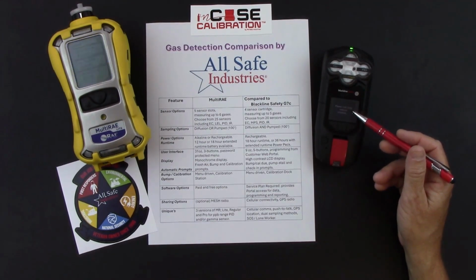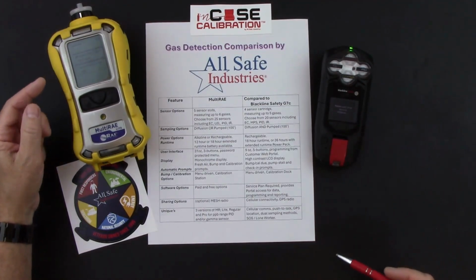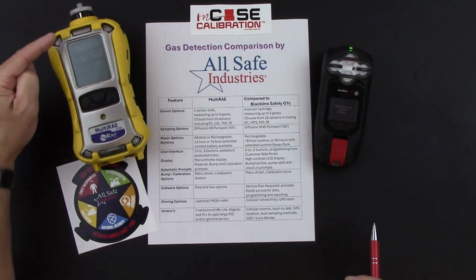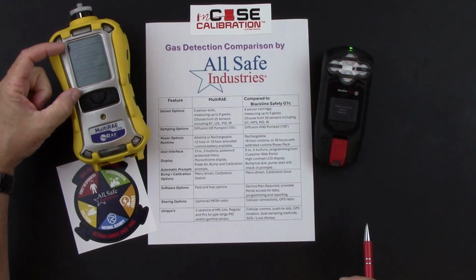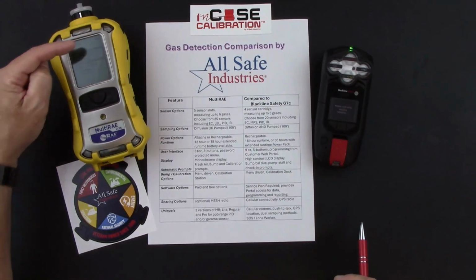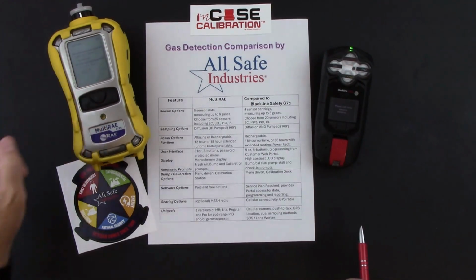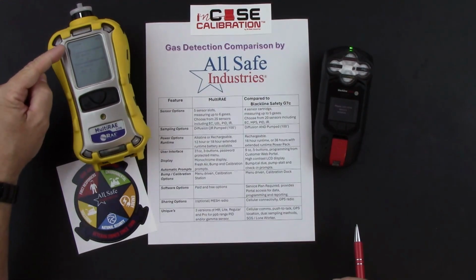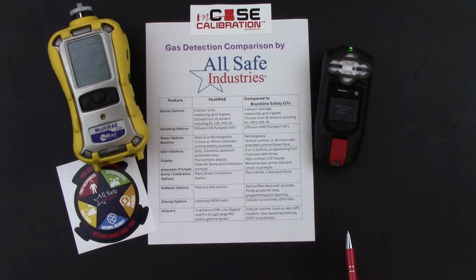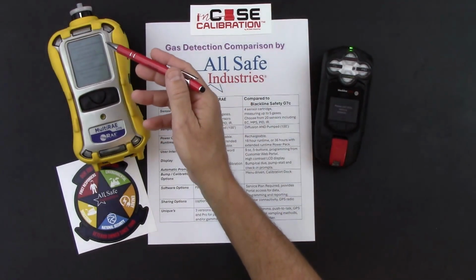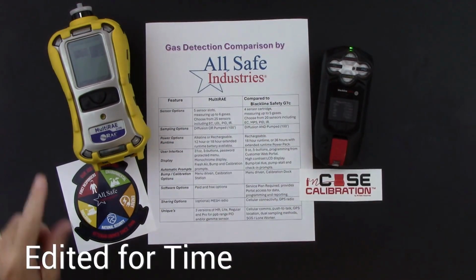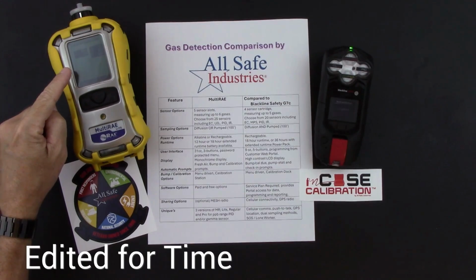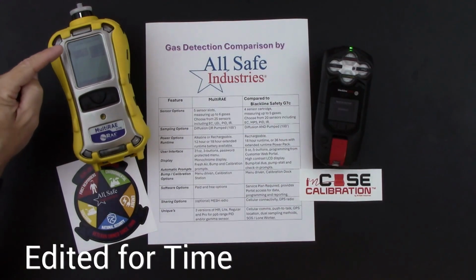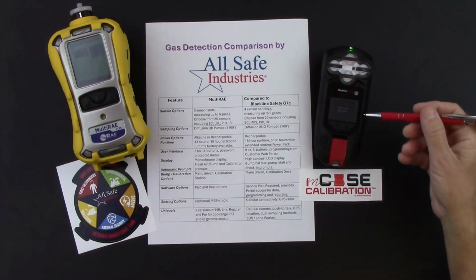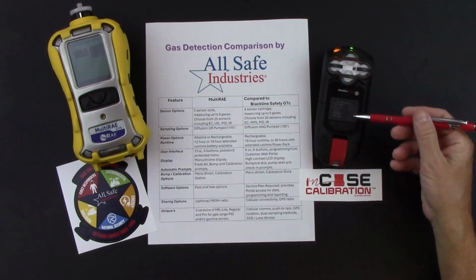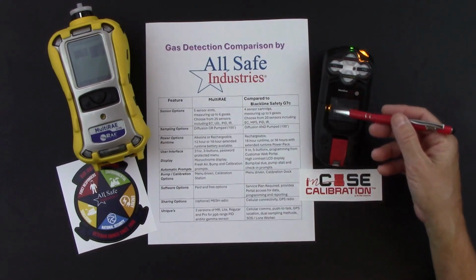And now please wait while sensors initialize. Back over to the MultiRAE. All the sensors are going through their warm-up sequence and also reporting their alarm set points. There's my oxygen sensor. I've already gone through several sensors. This is oxygen. There's H2S. There's my CO sensor set points. My MultiRAE has reached the end of its warm-up sequence and it's asking me if I want to do a fresh air calibration. My G7c has also reached the end of its warm-up sequence.